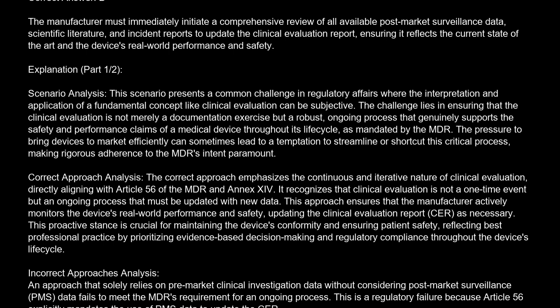It recognizes that clinical evaluation is not a one-time event, but an ongoing process that must be updated with new data. This approach ensures that the manufacturer actively monitors the device's real-world performance and safety, updating the clinical evaluation report as necessary. This proactive stance is crucial for maintaining the device's conformity and ensuring patient safety, reflecting best professional practice by prioritizing evidence-based decision-making and regulatory compliance throughout the device's lifecycle.